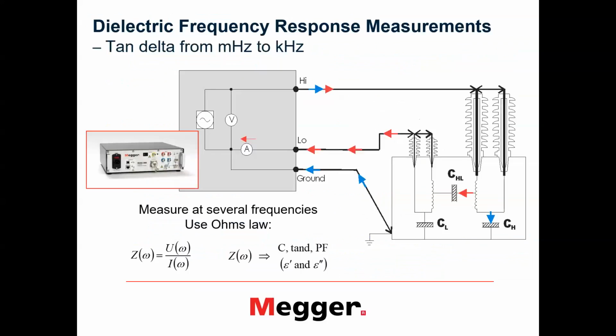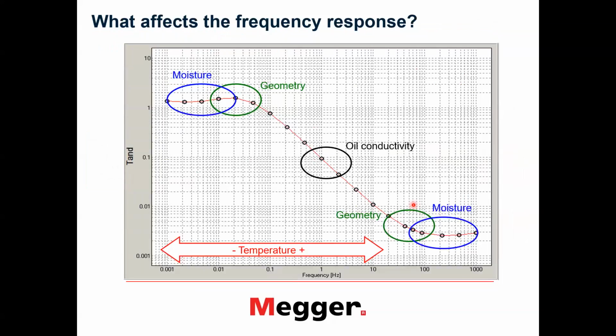So dielectric frequency response measurement is quite similar to SFRA. We also have a generator and we have a reference voltage measurement, and then we measure current, and then we obtain the impedance of the test object, from which we can derive tangent delta and capacitance, which we then can plot as a curve in a frequency scale. And this is a curve which we analyze and which we use for moisture estimation in power transformers.